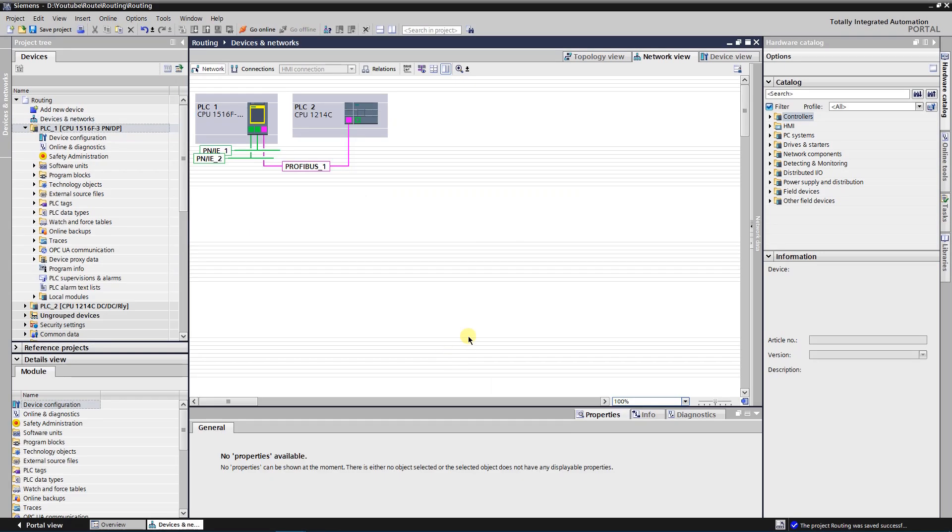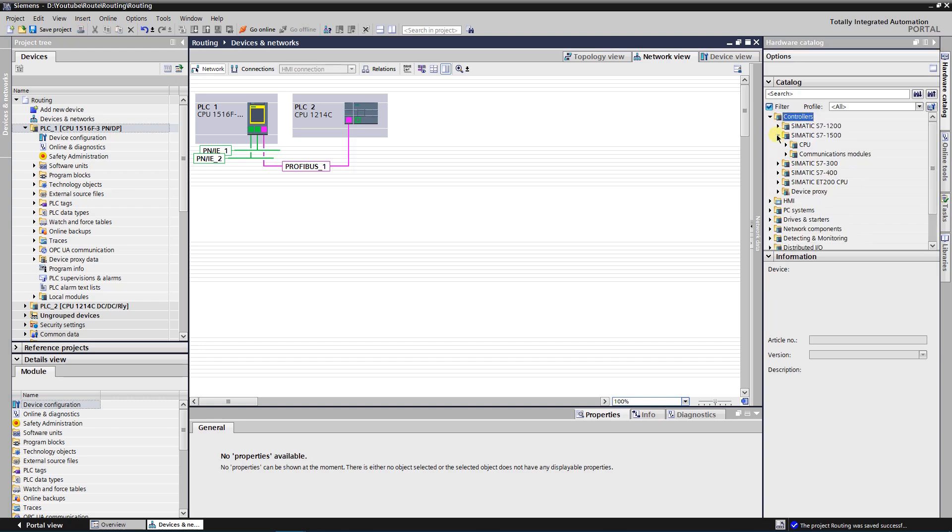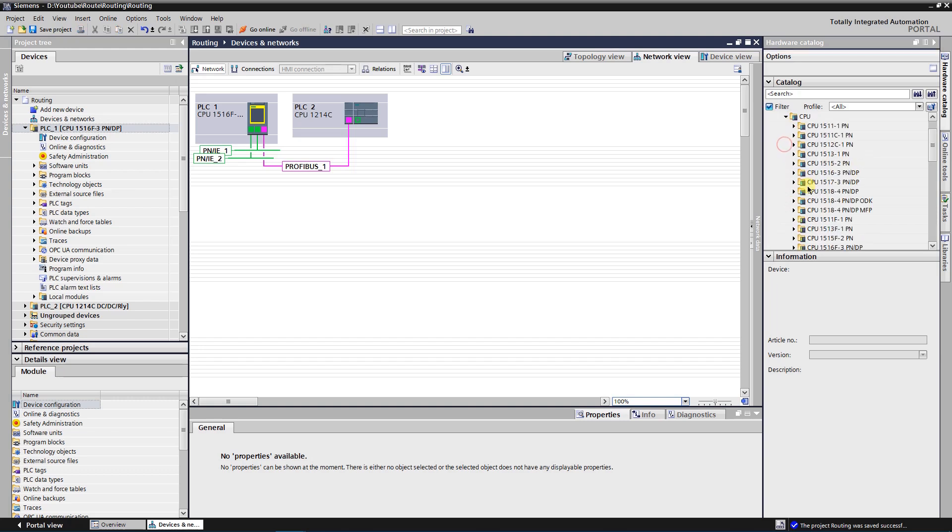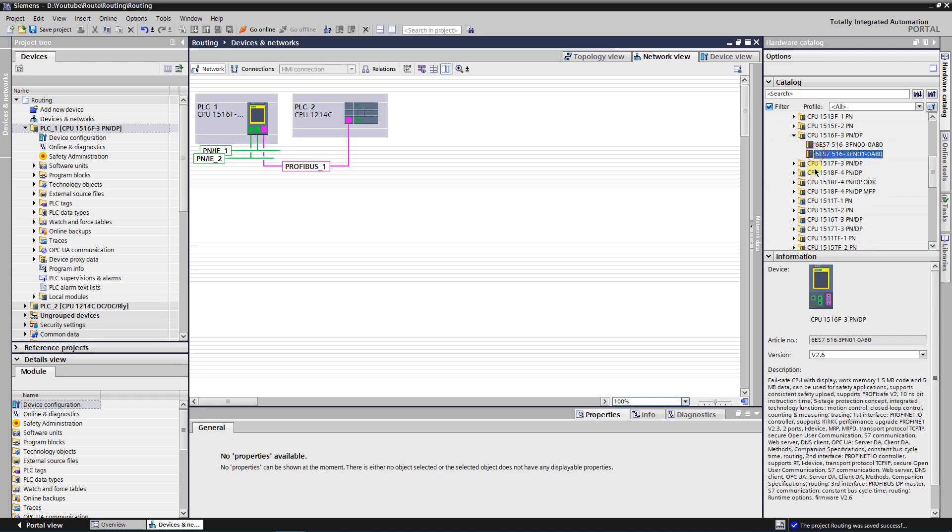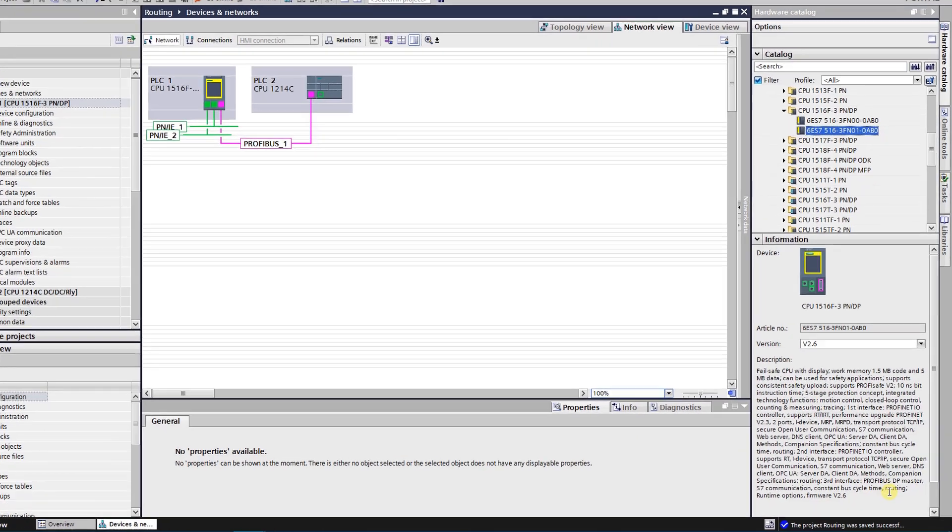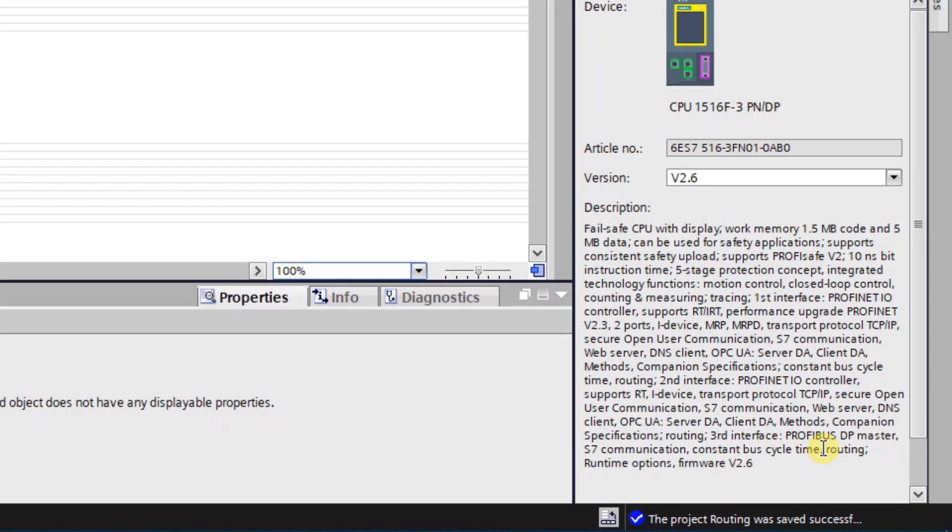First of all you need to make sure that your CPU supports S7 routing. You can find that information in the description of the CPU. All you need to do is browse the hardware catalog and find your CPU. Here you can see that my CPU supports routing. So I will be able to access the second CPU via first one.